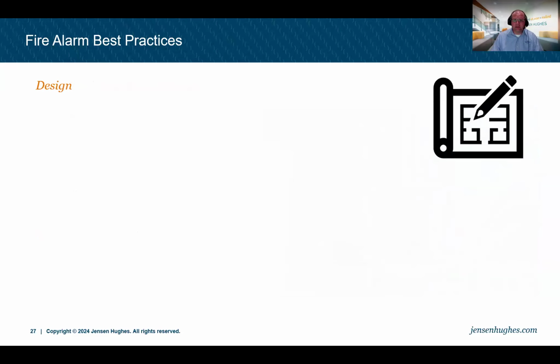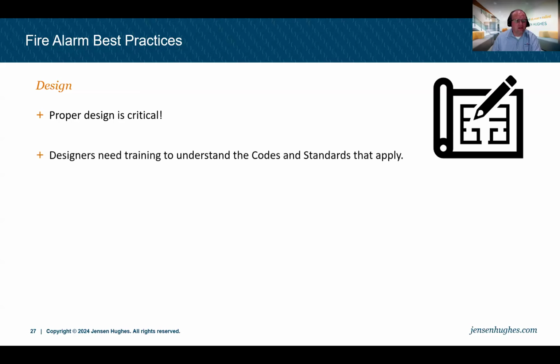Now, first, system design, especially a replacement fire alarm design, or maybe moves, adds, and changes, a tenant finish in your facility. The design is a critical best practice step to operational reliability that simply cannot be overlooked. A proper fire alarm design is critical, and often fire alarm systems are designed by individuals who don't have the appropriate fire protection background to perform the design competently. The designer needs to understand that applicable codes and standards are really just minimum criteria and provide only the minimum baseline from which to expand.